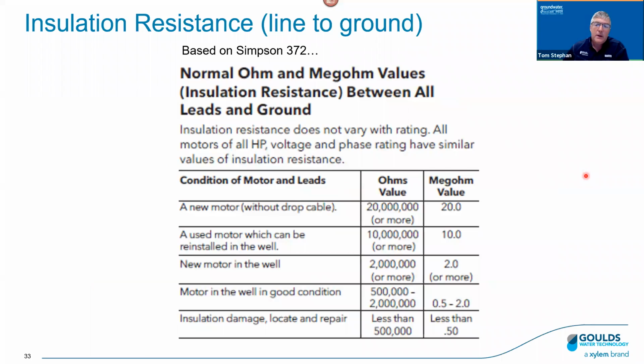The real beauty of those meters is, we'll see that in a second here. So in that spiral bound book, again, it's going to give you a chart, and the chart is in either ohms or megohms, and it's saying 20 meg or greater, right? It's a new motor, all the way down to less than 0.5 meg or 500,000. We've got a problem. We've got to pull it and see what's going on. So it's a nice little chart that's provided, but keep in mind that it is based on the Simpson 372, which puts out 50 volts.